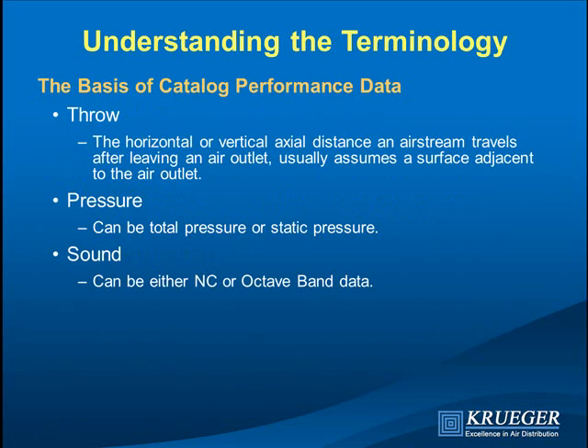When we put data in the catalog, we talk about three main things. Throw is the distance the air travels along, typically along a surface — there are exceptions. Pressure: we talk about total and static in the catalog, and you can calculate velocity pressure very easily. And sound: Krueger is the only company that lists octave band data for every diffuser, and we also calculate NC.